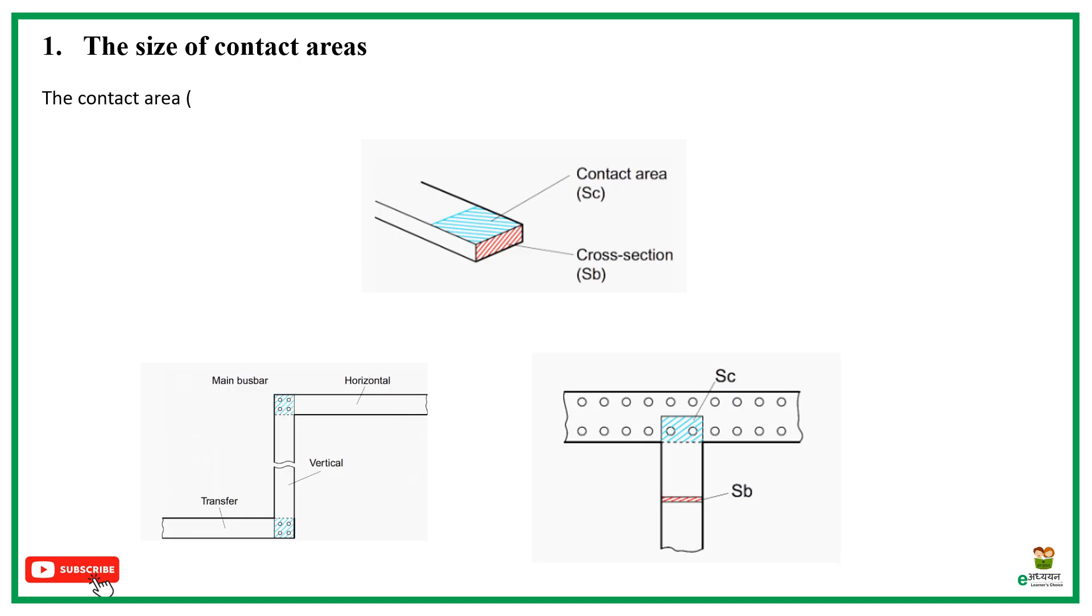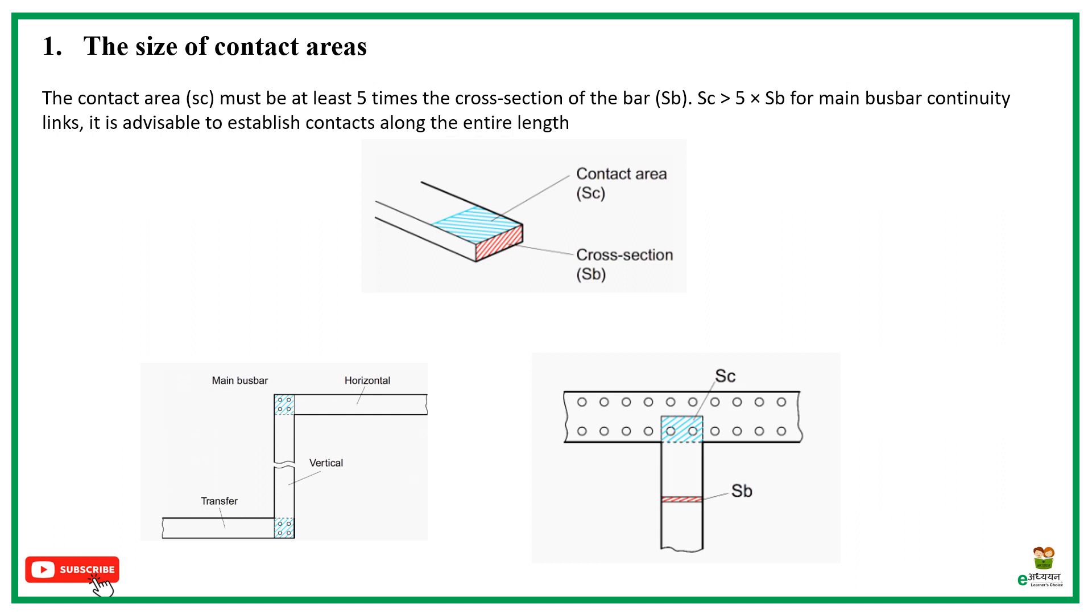The size of contact areas. The contact area SC must be at least 5 times the cross-section of the bar SB. SC is greater than 5 times SB for main busbar continuity links.